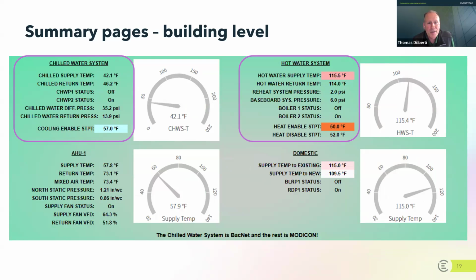Another screen here, wanted to point out a couple things with this, and I'm going to flag on this example, this idea of a cooling enable set point and then heating enable and disable set points. So let me take you through a scenario here. Let me take you through one similar to what I had given you earlier, where it's a colder day that gets warmer. What this does is when you see these values here, this is saying when the temperature is less than 50 degrees, the heating system is going to be enabled. So it means you're going to have access to hot water and heat in the building.